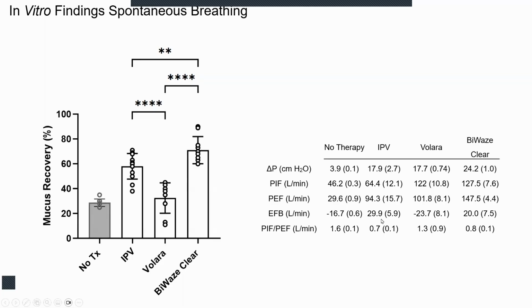You can see here that the IPV's expiratory flow bias is approximately 30. With the BiWaze Clear, it's about 20. Nonetheless, I think applying this at a higher pressure allows the secretions to come out of the lung a little better. So it's a question of what you want to do differently: use slightly higher pressures, or change the timing by which you put the gas into the lung and take it out? Overall, these were very effective therapies for getting a majority of the secretions out of the lung.